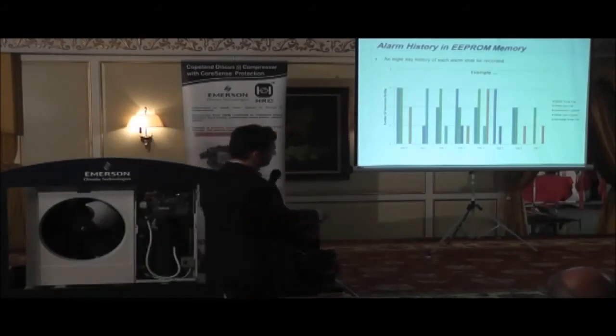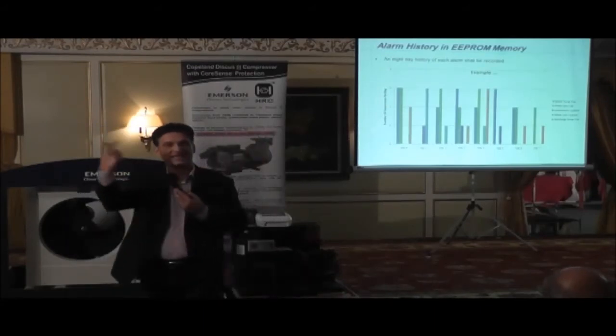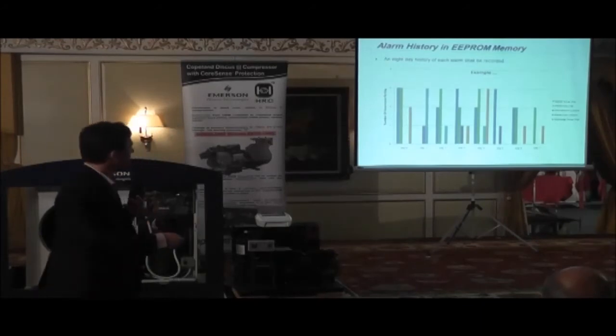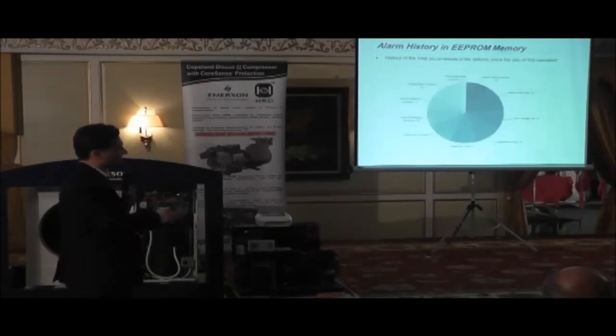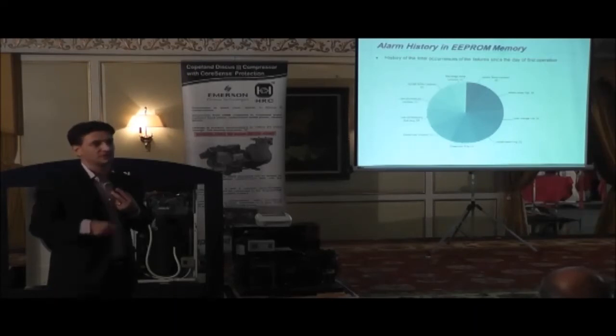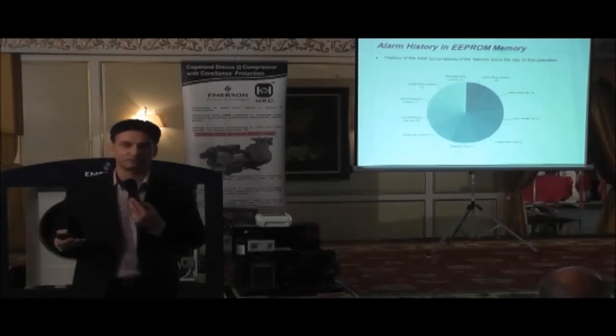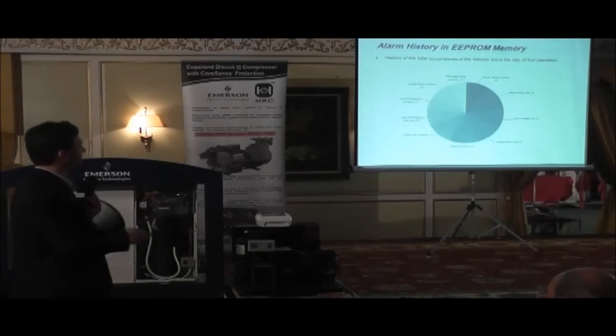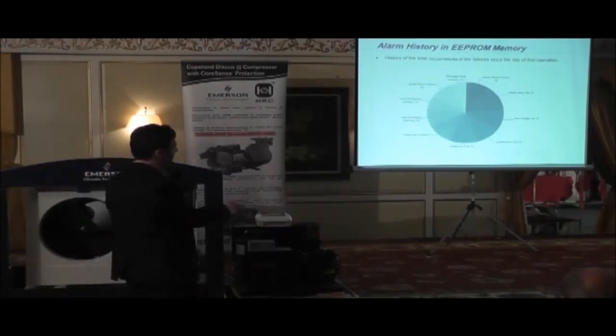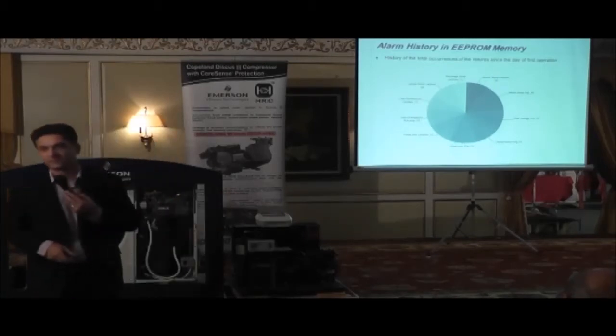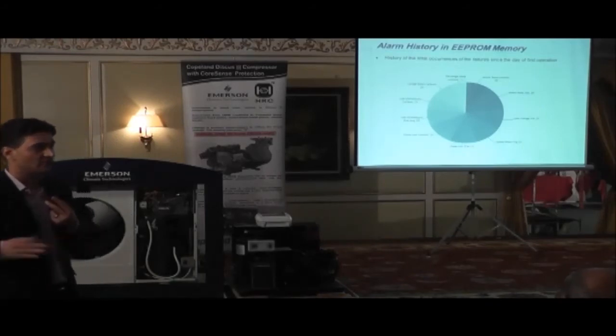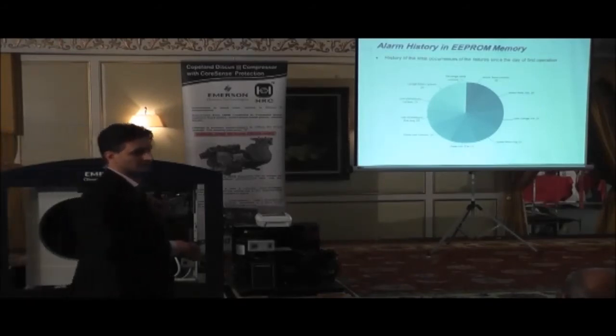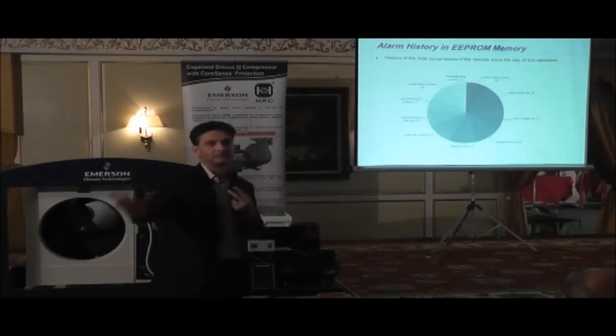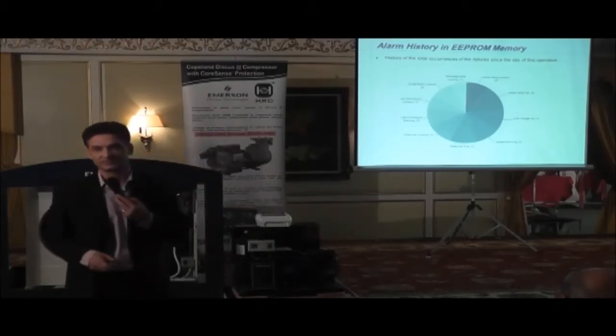Now once we get to day 7, we allocate a counter. Alright? And that counter gets allocated to the main trip condition. So even after 2, 3, 4 years, when you connect your PC to the compressor, it will tell you that this compressor has been running for 4 years, and in that time I've had 20 motor temperature trips, 15 low oil pressure trips, etc. So it will give you the complete operating history from day 1. Okay? Until the compressor gets replaced or until it's reached its runtime.